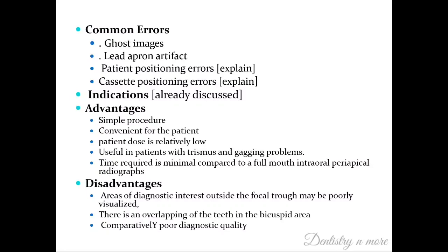Patient positioning errors are based on proper placement of the patient within the focal trough, which is necessary for diagnostic panoramic radiographs. If out of the focal trough, certain errors occur. If the patient is positioned too far posterior relative to the focal trough, the image is magnified in the mesiodistal dimension — the teeth look fat. If the patient is positioned too far anterior in the focal trough, there is a reduced mesiodistal dimension in the anterior sextant. Cassette positioning errors are also explained in this chapter. The indications were mentioned in the previous section.